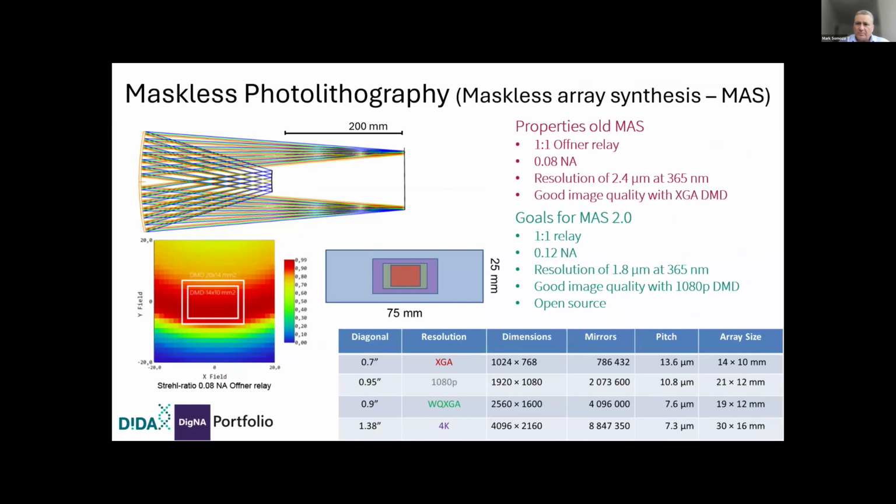The original approach used by Nimblegen was to use an optical system that's shown here. It is just a curved mirror or two curved mirrors, and we have a digital micromirror device at one place, and we illuminate it. The reflection from the mirrors that are tilted hits one optical surface, reflects to another optical surface in the back, and is then imaged onto a glass surface. That glass surface is where we do the spatially sensitive deblocking with photolabile groups.